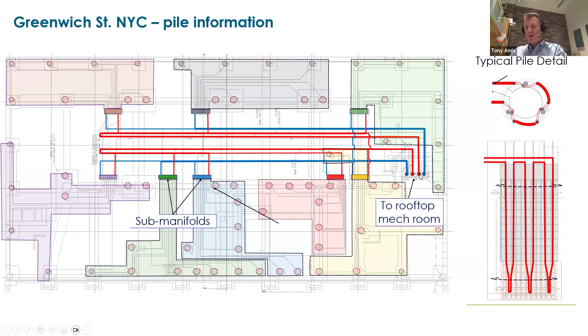Coming back to that energy model and the building heating and cooling load, this is the timeline of what we expect in the ground, the changing ground temperature over 240 months, 20 years. Ideally, and we have designed projects in central London for Crossrail that had a 150-year design life. The important thing is that there's a monitoring system installed into these systems that measures the performance and ground temperature, and has the ability, if the gradient on this temperature increase is too steep, to adjust it. Because you probably won't know there's a problem with the heat pumps or with the ground loop until five or six years' time, by which time you may well have taken out too much heat or put too much heat back in the ground, and your heat pumps will just go into fault mode.